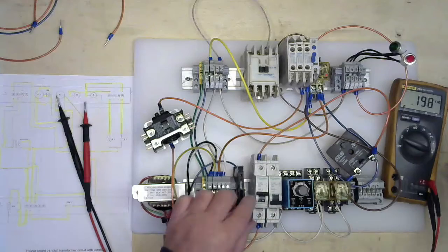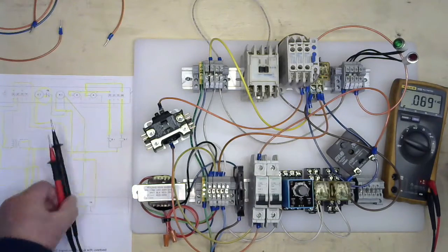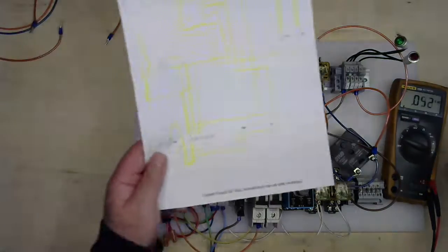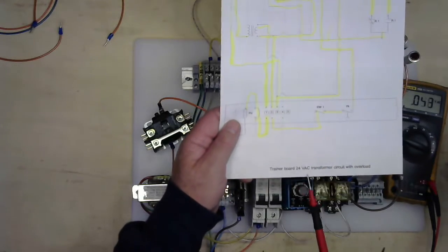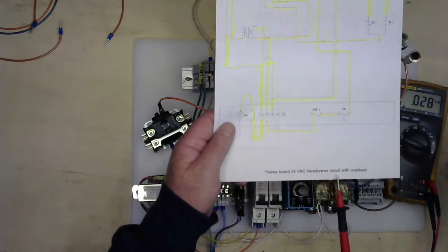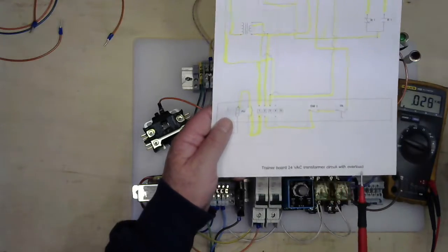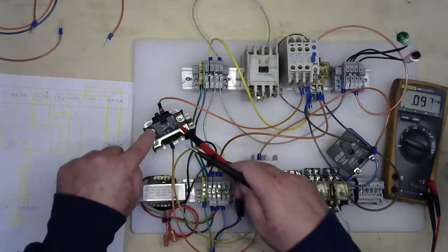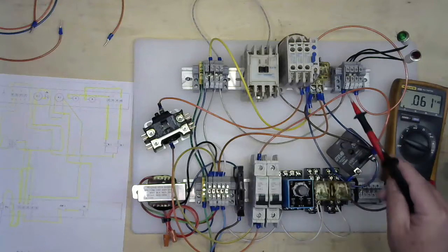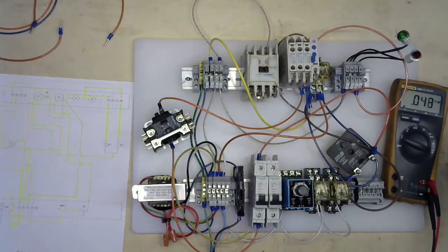So that's the board that we have here. This is the training we have set up. You will wire up a trainer board 24 volt transformer circuit with overload. And the overload is only protecting the contactor. The relay will switch the lights back and forth using a 24 volt time delay setup with all the training. You see the wiring here can get cumbersome. That's why it's easier to use a highlighter to review the lights you have and go from there.